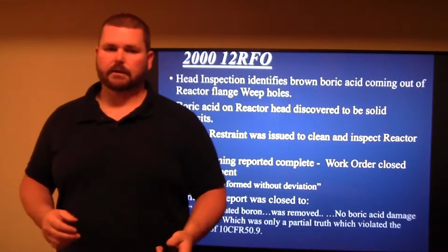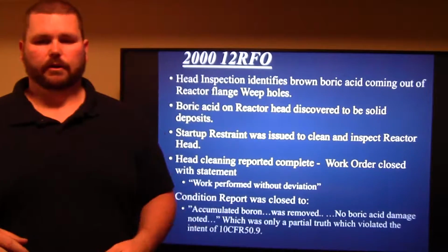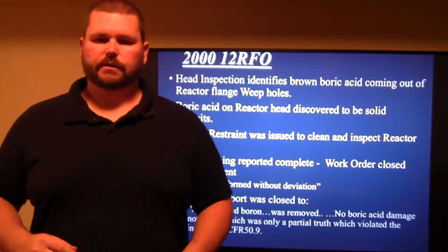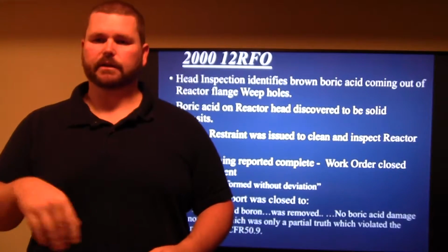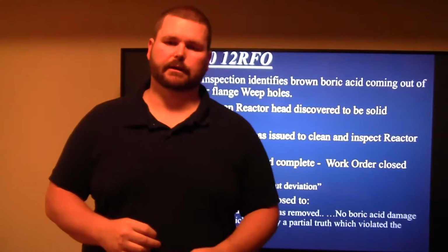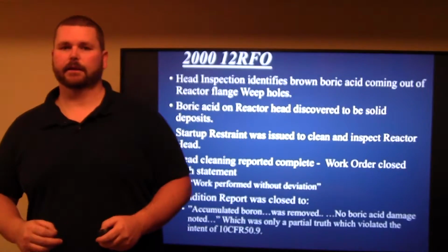So they closed out the notification saying, a startup restraint, we cleaned it, we had no more issues. What they actually did, they did a partial inspection. They didn't do all the inspection, they did a partial inspection. And this is actually a violation of the 10 CFR, saying it's not the full truth.